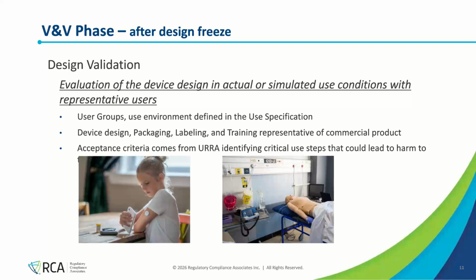Once we have a design freeze, we've designed the device, we've done formative evaluations, we think we've got this nailed, then we do a design freeze and we enter the verification and validation phase. Now this is where design validation comes in. Design validation is evaluation of the device design in actual or simulated use conditions with representative users.